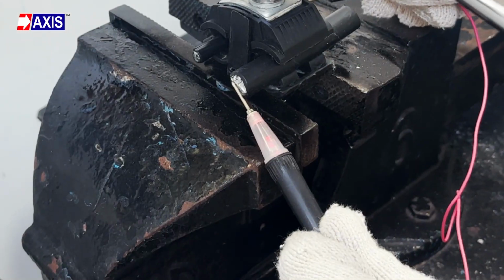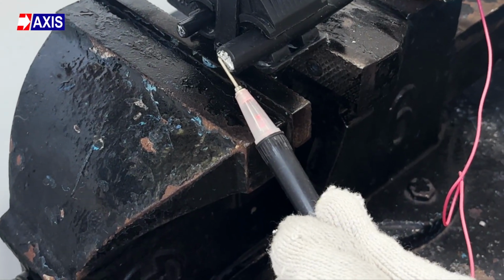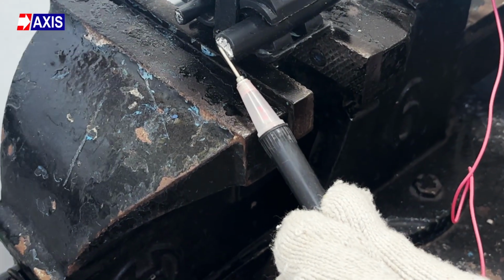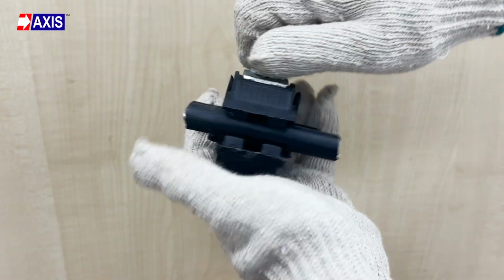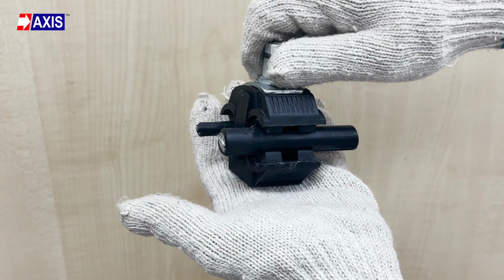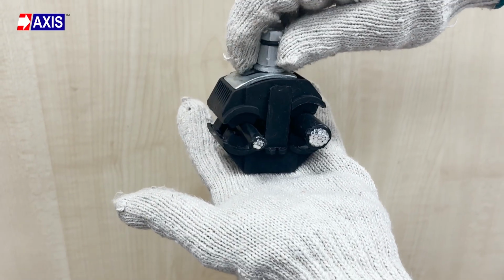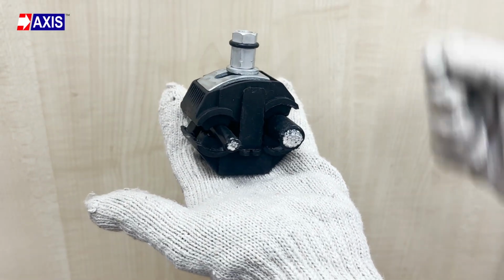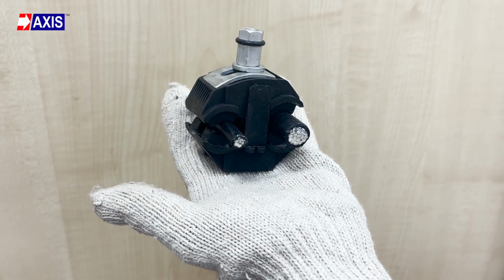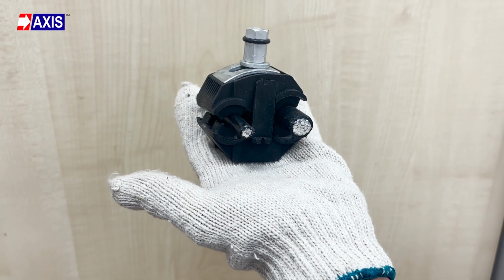As you can see, the lights on the continuity tester are blinking, which means electrical continuity is achieved and there is no mechanical damage. The Axis MV IPC has passed the test as per EN 50397-2, proving it can perform reliably even in freezing temperatures.